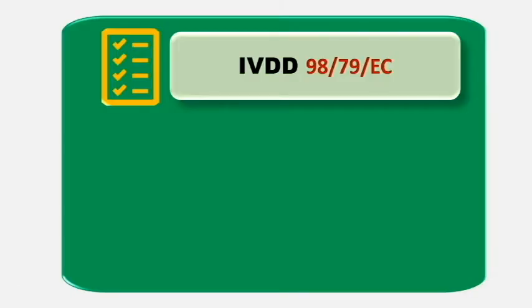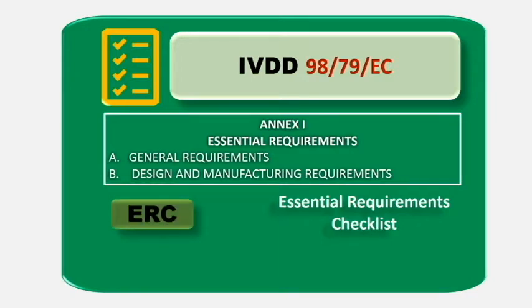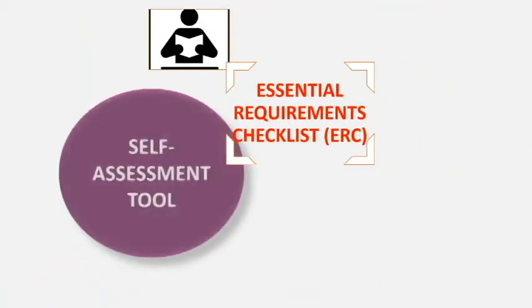Before going to GSPR, we will go through essential requirements first. IVDD Annex 1 contains essential requirements covering general requirements and design and manufacturing requirements. The essential requirement checklist is commonly known as ERC. Not all essential requirements will be applicable to all devices — the manufacturer will have only certain criteria applicable to their product. The manufacturer has to demonstrate conformity with these essential requirements. The ERC checklist serves as a self-assessment tool.